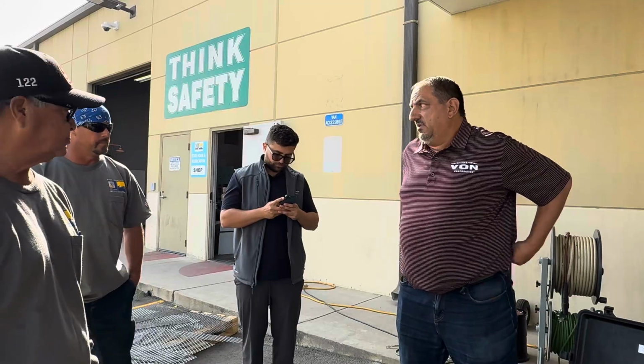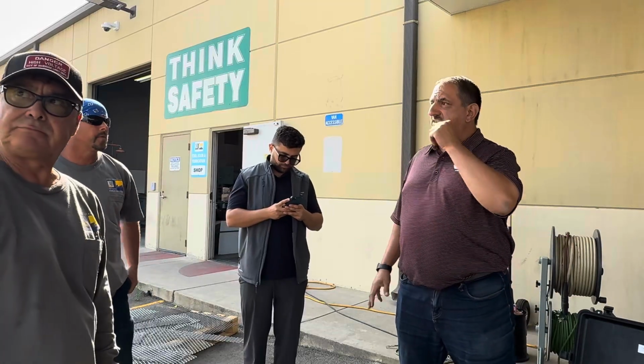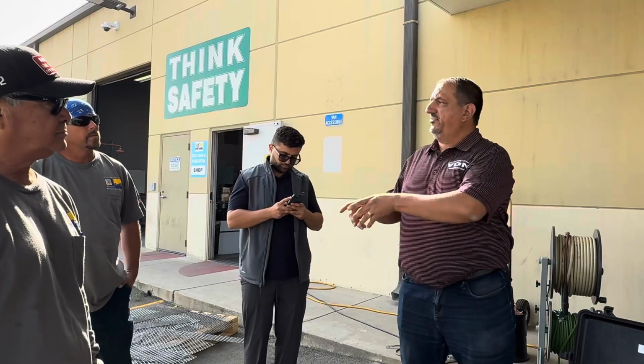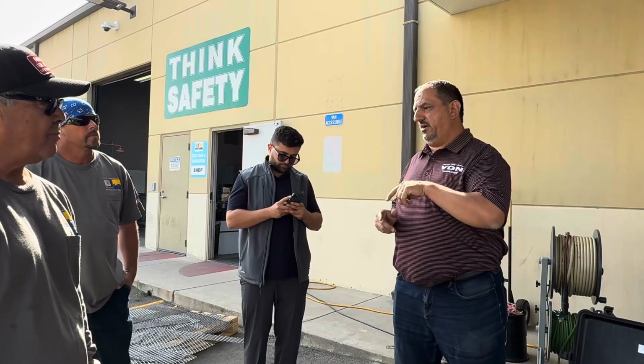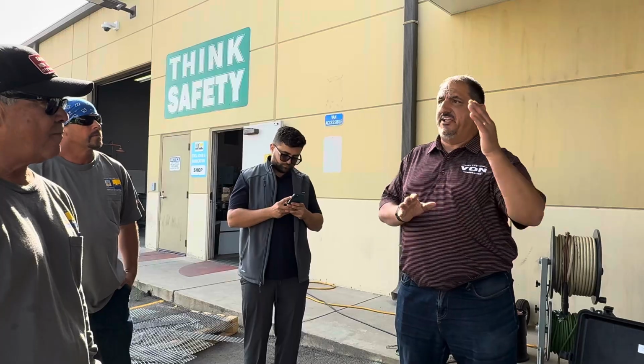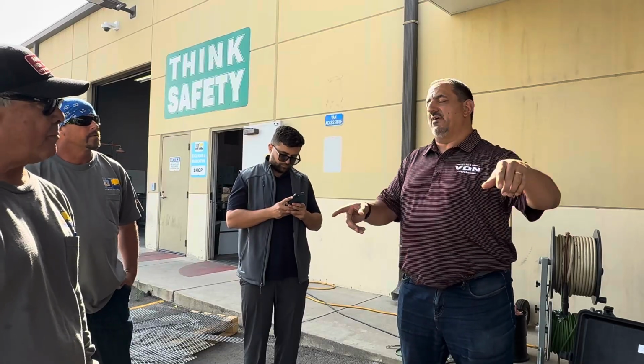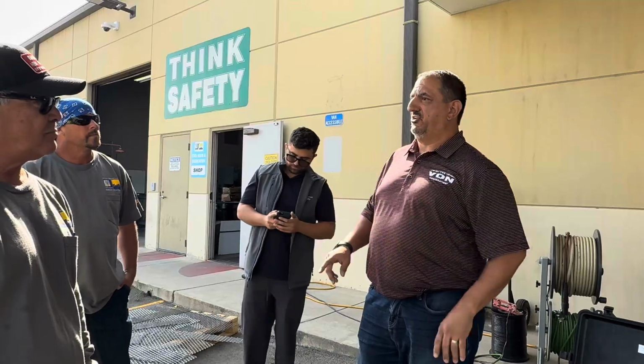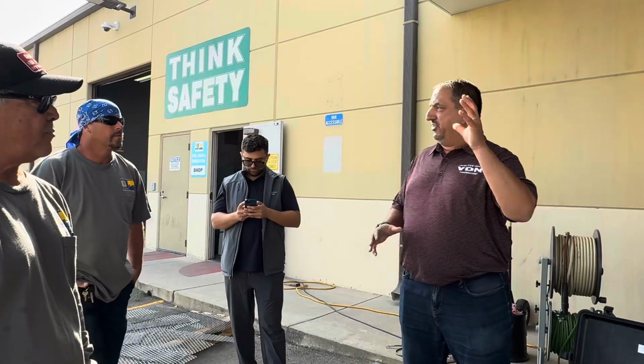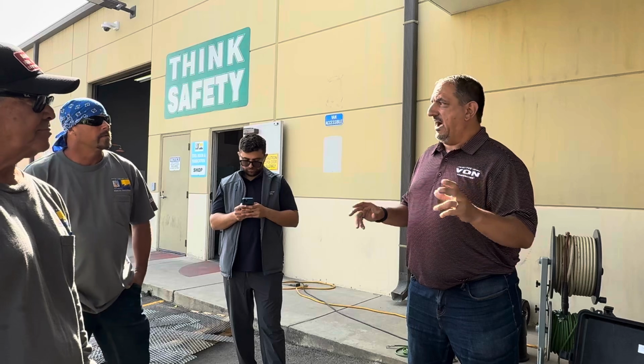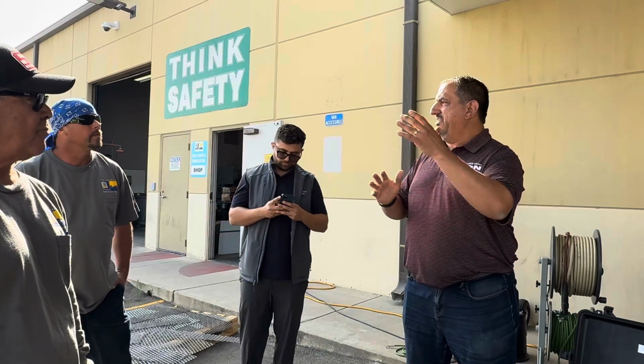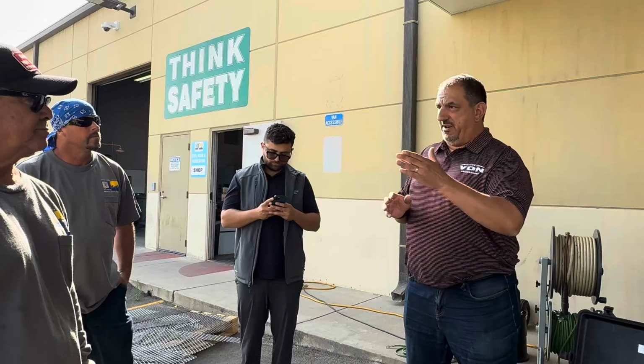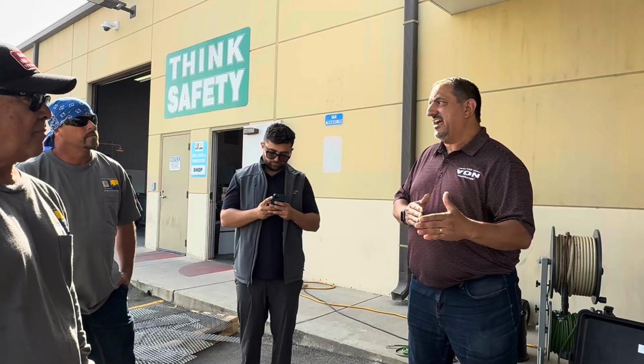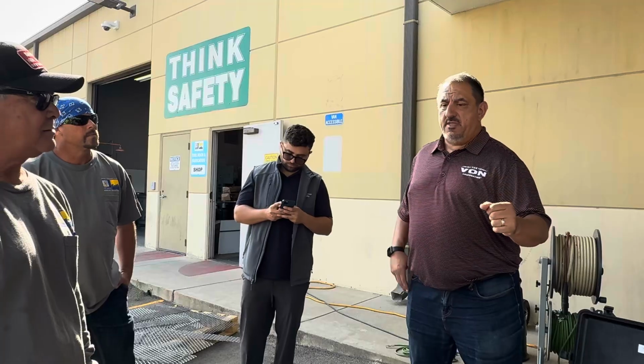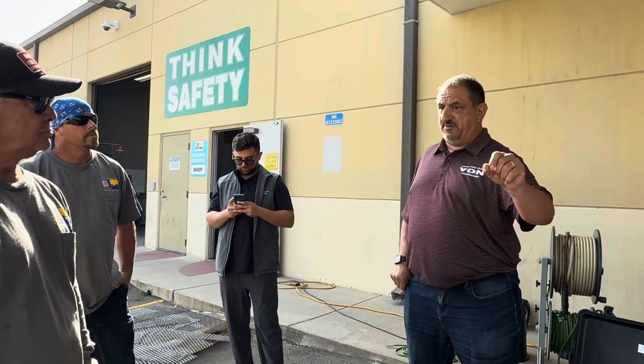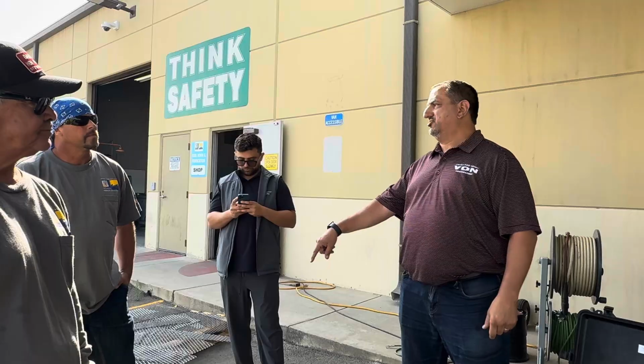If you have a lot of distance, we've done this in a training yard where they'll put a fault in the cable. They'll drill a hole to create a fault, and on the other end they just cut it, and then we will get it. When I think of utility, like 'in the clear,' I feel like you got either an elbow on the end of it or you peeled it back. But if you just cut it and call that in the clear, that's technically another fault. Sometimes it would spark in there, and sometimes that would show the fault where the hole they drilled didn't.